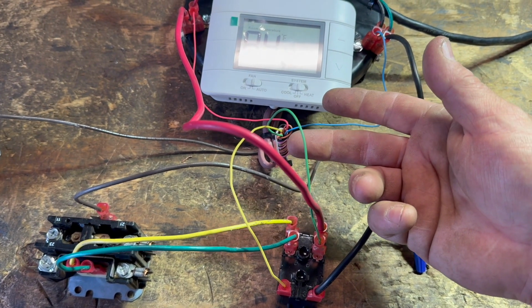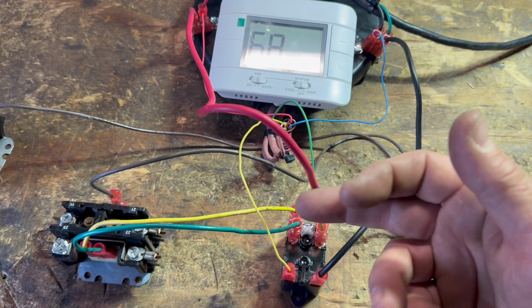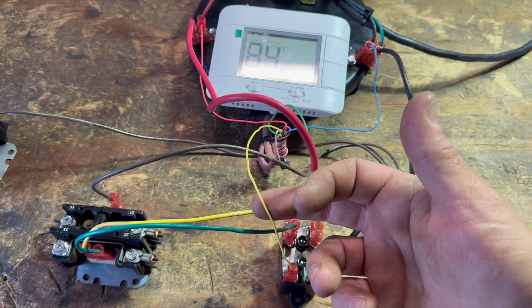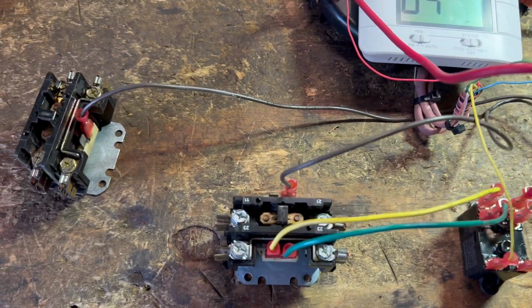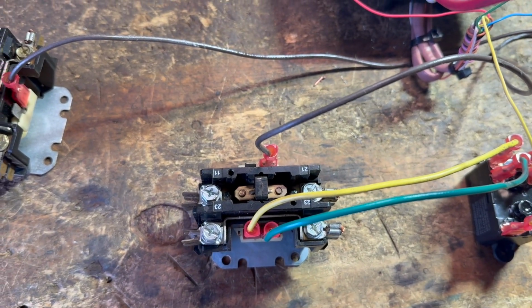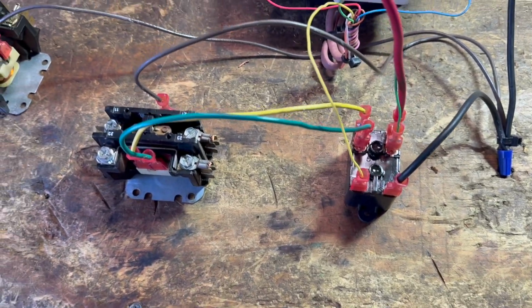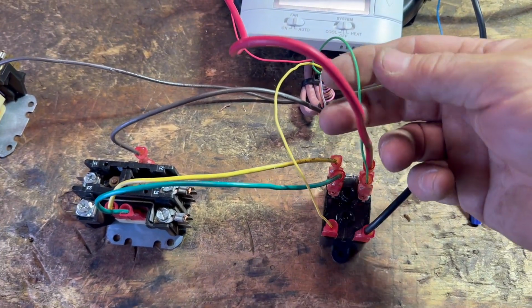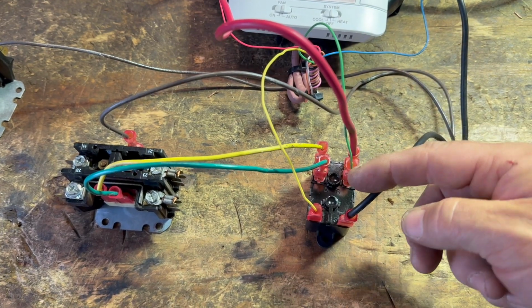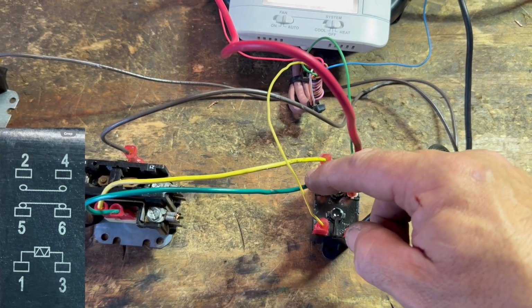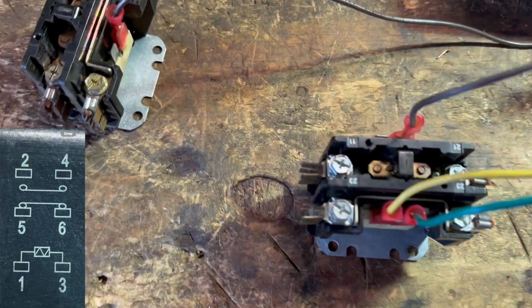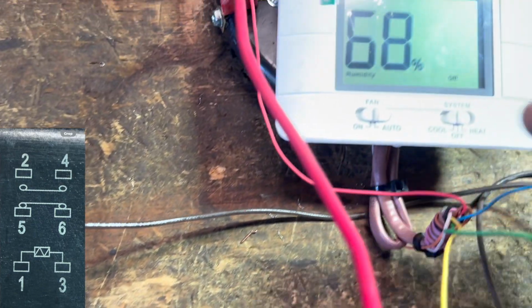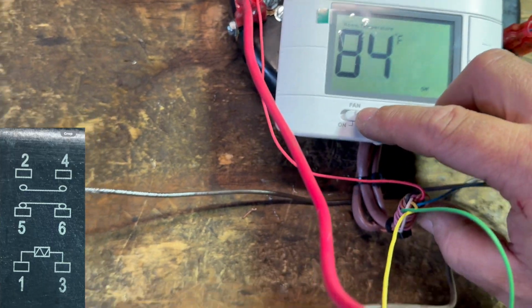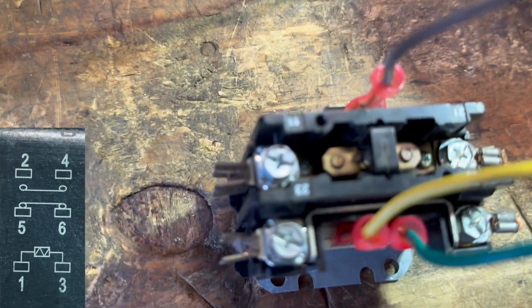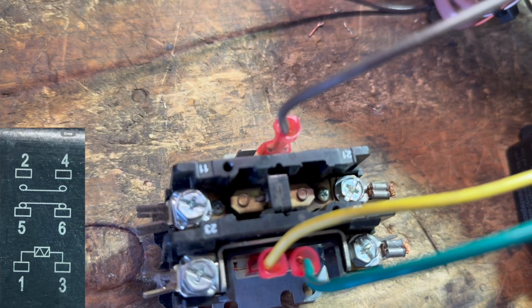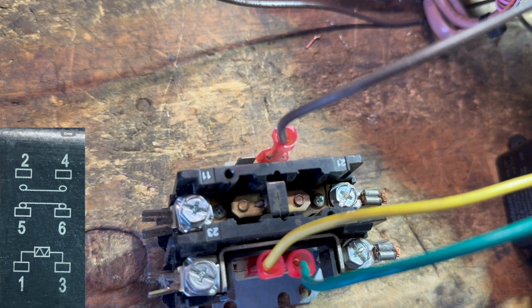Green is a call for our fan to come on. Yellow would be a call for cooling to come on. Let's say this is our load for the fan. Okay, so every time I have an input for the fan, it's going to come in here and go out through this green wire to activate this load, and you'll see this suck in. Once I turn this fan to the on position, I'm going to go ahead and do it, and you can see the contactor physically suck in. Okay, so that's with the fan on.